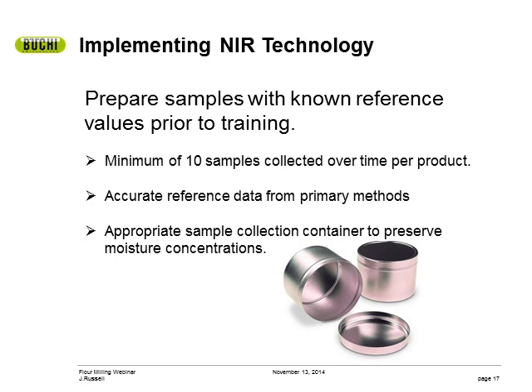Some of this should go without saying, but I want to bring it up because I have installed a lot of NIR spectrometers in which the laboratory did not have any samples prepared, or they used their current NIR as reference data, or the sample sat for long periods in plastic bags losing moisture. When this happens, the customer does not get the full benefit of implementation while the NIR expert is on site. When I say collect 10 samples per product, this means 10 hard wheat flour samples — spring or winter wheat, that is fine. If you run soft flour or whole wheat flour, collect 10 of each of those as well.